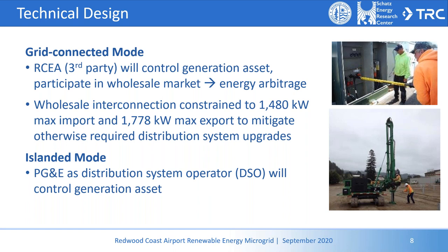We chose, through our interconnection process with PG&E under the wholesale distribution tariff, to constrain our interconnection to the numbers you see there for import and export. We did that in order to mitigate upgrades that would have been required to the distribution system to handle the full nameplate capacity of our system. By constraining the output and input, import and export, to those values, we were able to mitigate that cost and really make the economics viable for our project.